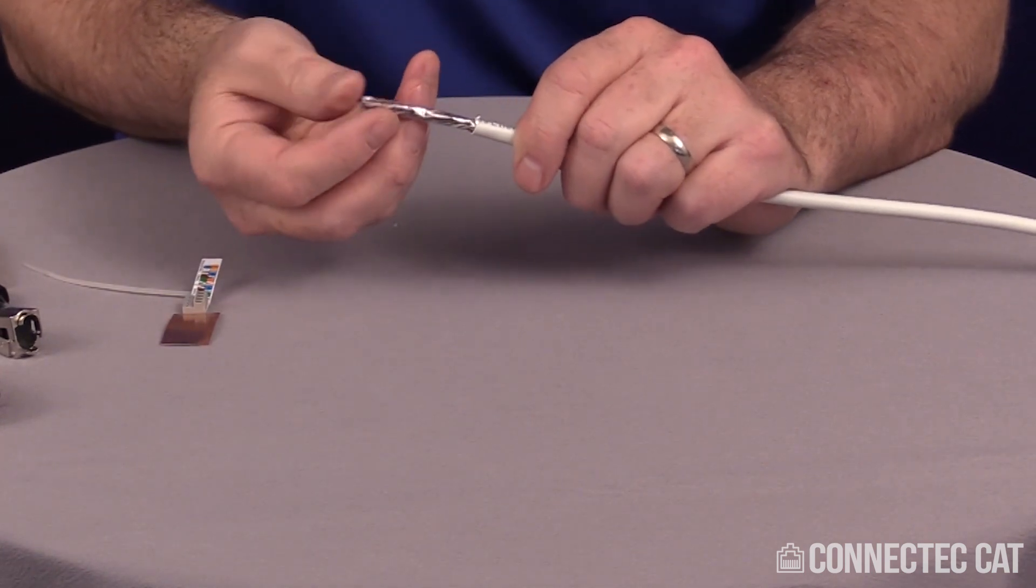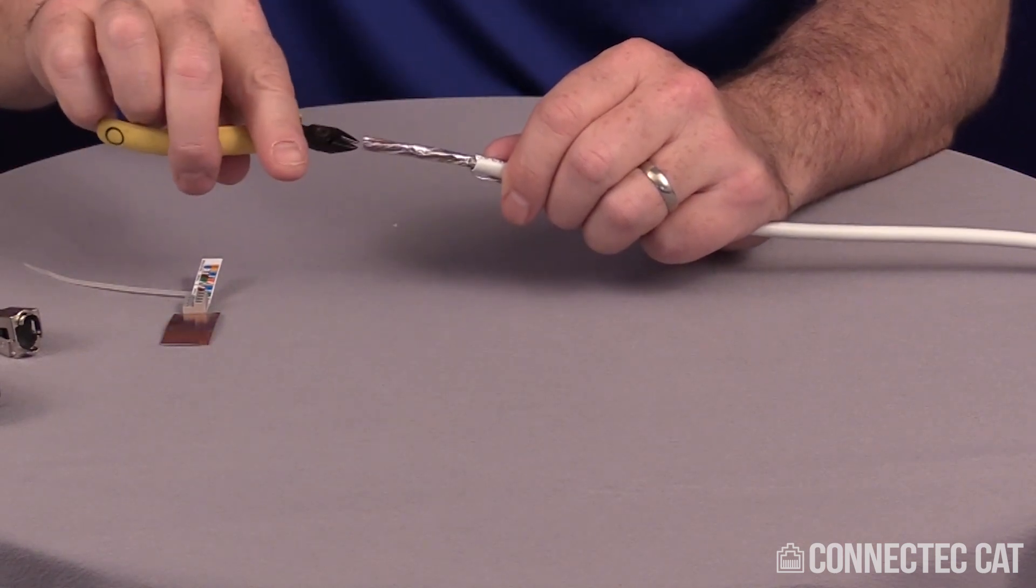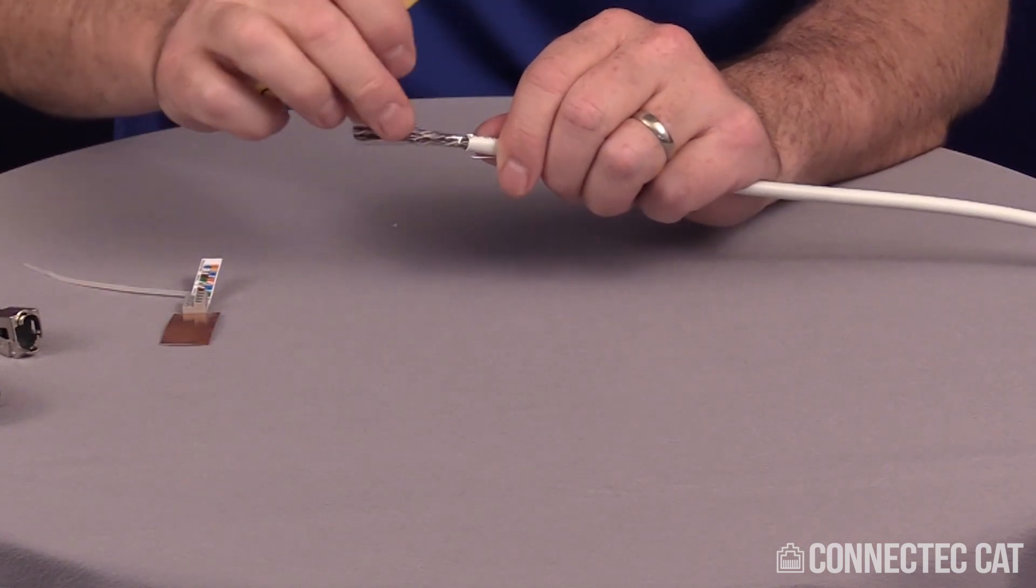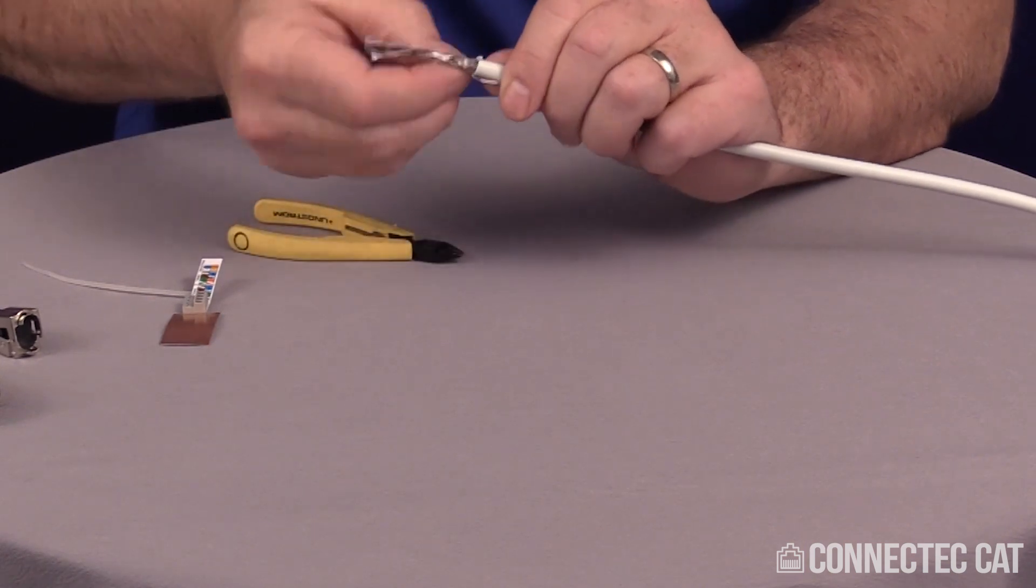Find your drain wire and fold it back. Do not cut it off. Now remove your polyester binder, this clear binder here. Find the seam on that one also, follow it down to the jacket, nip it, and it'll come right off.